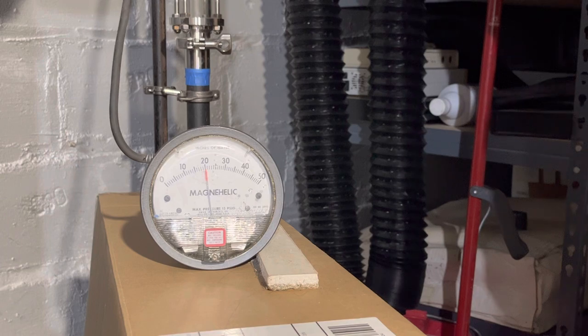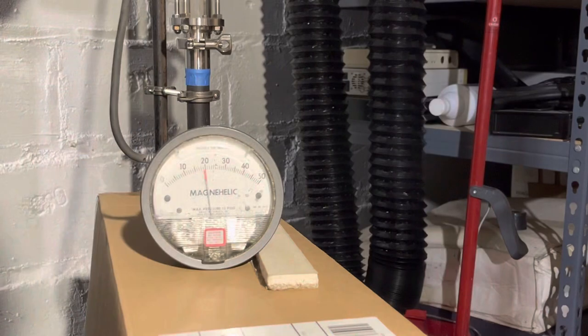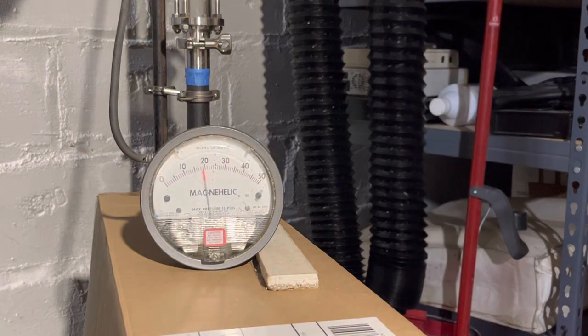Yeah, do you hear that? Yeah, that's my main vent opening, and it's making a little bit of a hissing sound. So right now it's letting out. It opened because it got cool, and now it's letting the last of the pressure out of my system. Pressure is also going away because the remaining steam upstairs is condensing.